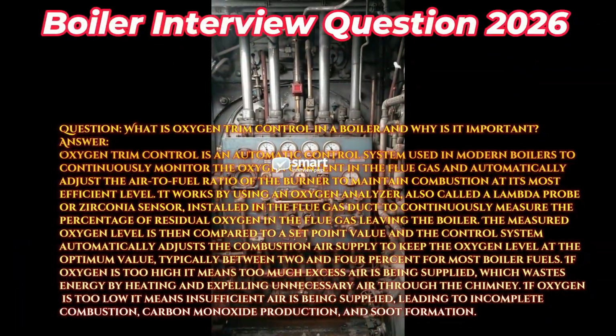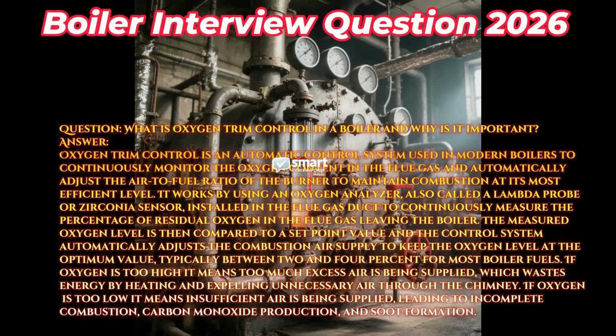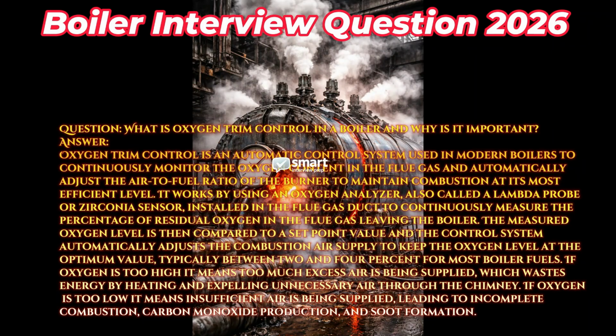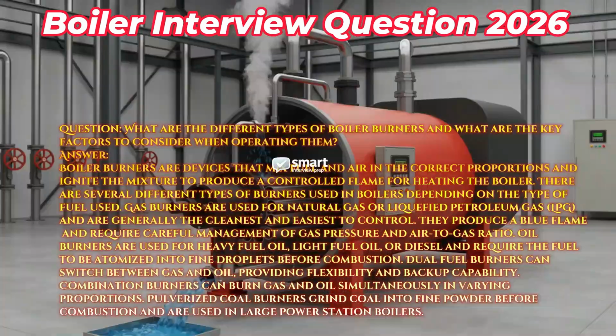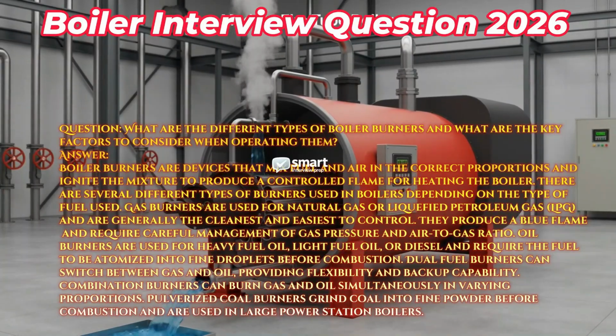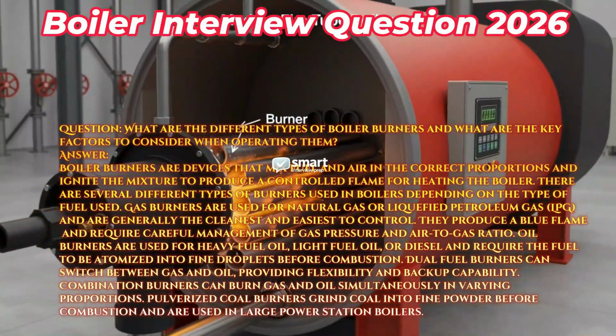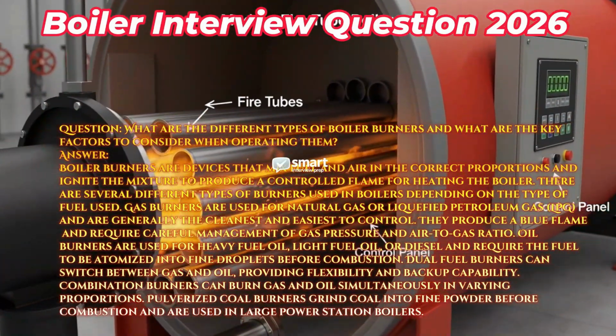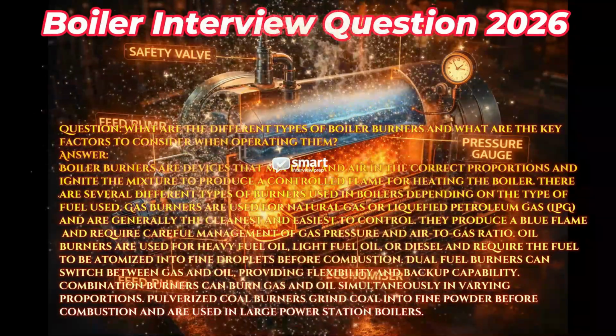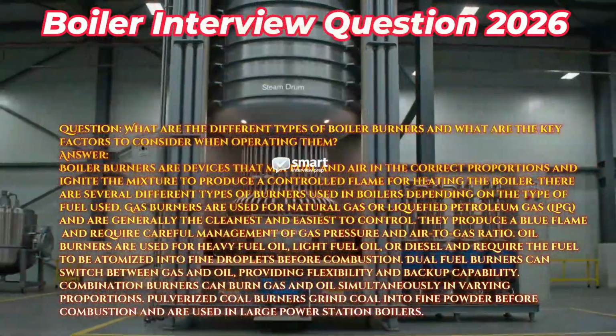If oxygen is too high, it means too much excess air is being supplied, which wastes energy by heating and expelling unnecessary air through the chimney. If oxygen is too low, it means insufficient air is being supplied, leading to incomplete combustion, carbon monoxide production, and soot formation. Question: what are the different types of boiler burners and what are the key factors to consider when operating them?